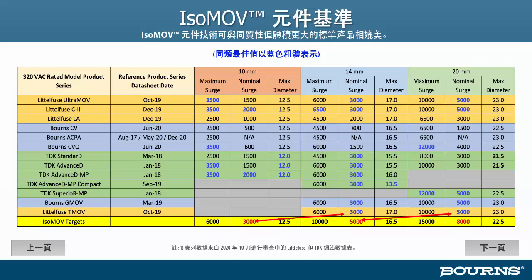This means designers specifying higher voltage rated MOV devices to achieve acceptable design margins may find that a smaller IsoMOV device with lower protection voltages is the right choice. Choosing a higher voltage rated MOV won't be necessary because you've got the MOV and the GDT in series that can tolerate the temporary overvoltage events. Another important benefit to the lower clamping voltage design is the possibility of employing lower voltage rated components downstream. Other designers may have specified a higher surge rated MOV than they thought they might need to ensure longevity. The IsoMOV protector has the added surge capability in a smaller size. Alternatively, a designer may opt for an IsoMOV device in the same size and enjoy a longer service life or higher surge ratings. Designers have many options available to do cost downs, to do size downs, and to generally improve the overall safety and performance of overvoltage protection in their products.